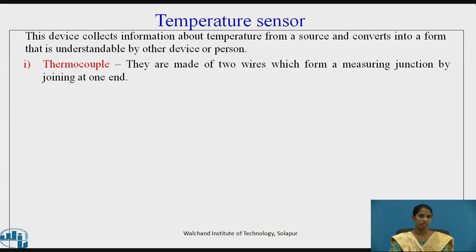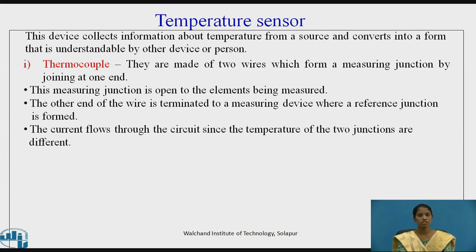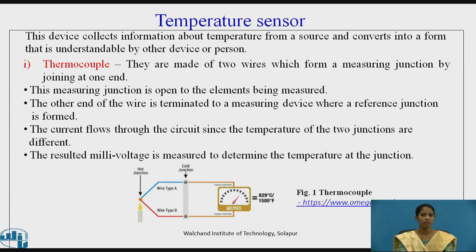The first temperature sensor is the thermocouple. A thermocouple is made up of wires which form a measuring junction at one end. This measuring junction is open to the elements being measured, and the other end of the wire is terminated where a reference junction is formed. Current flows through the circuit since the temperatures of the two junctions are different. Figure 1 shows the thermocouple, with a cold junction and a hot junction, and two wires of type A and type B.